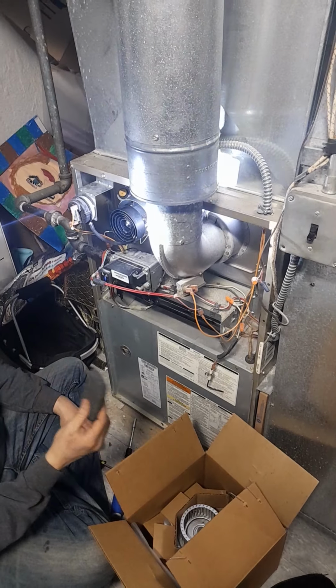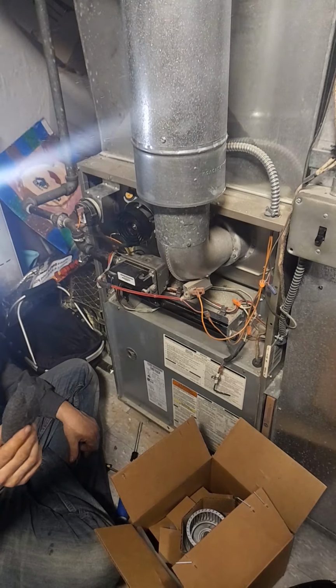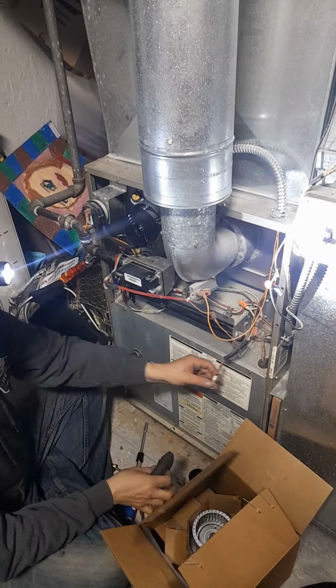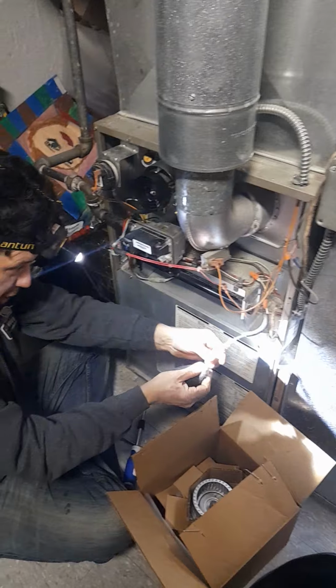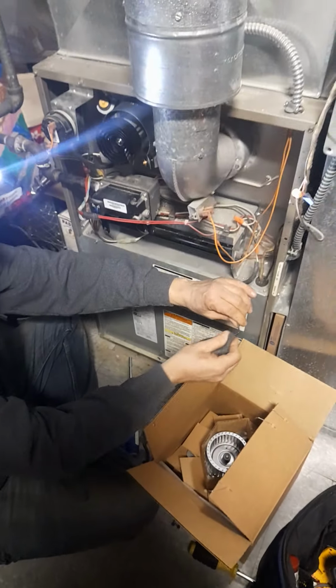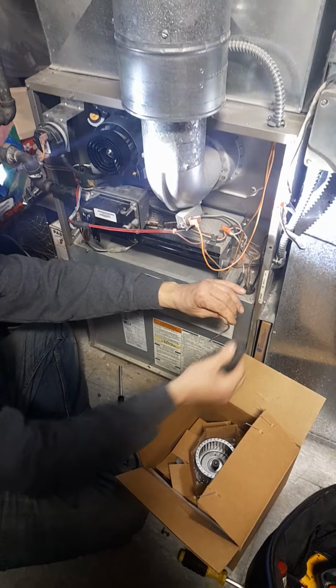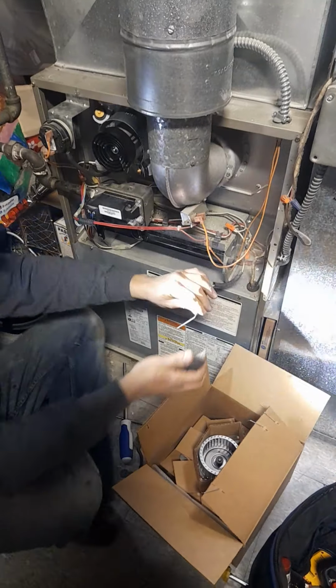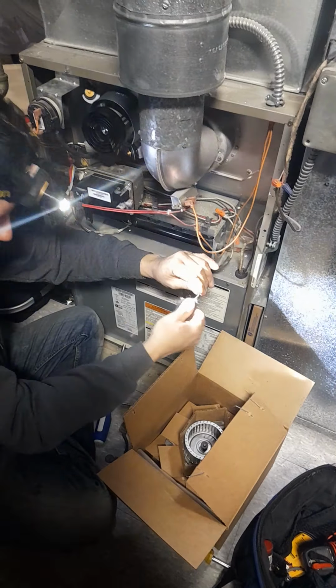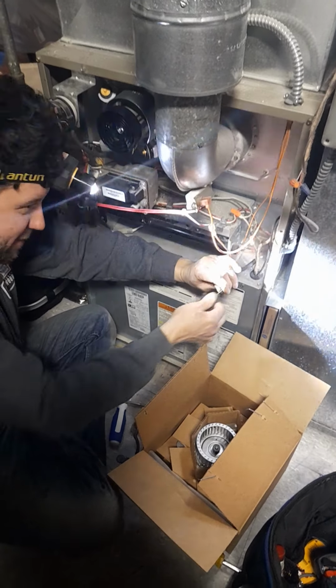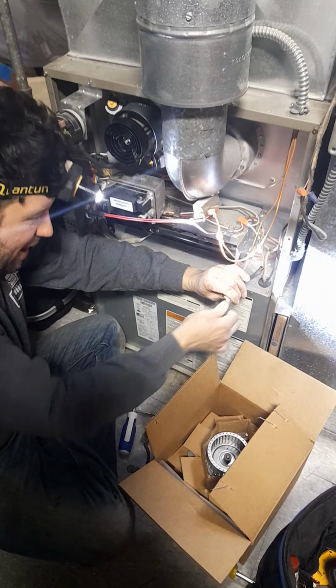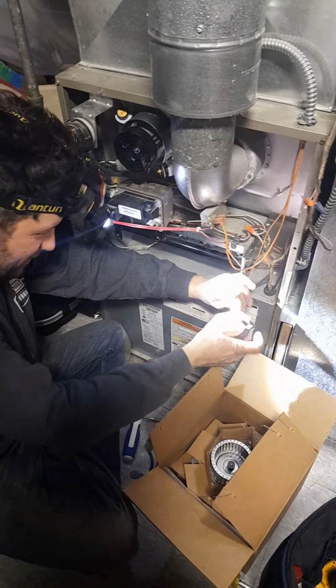Never, ever use sandpaper. Because sandpaper will leave sand particles. And what happens when you melt sand? You get glass. And what is glass? It's an insulator. So you will have made your problem worse because then you've got a glass insulating layer on top of your flame sensor. Then it doesn't work for sure.